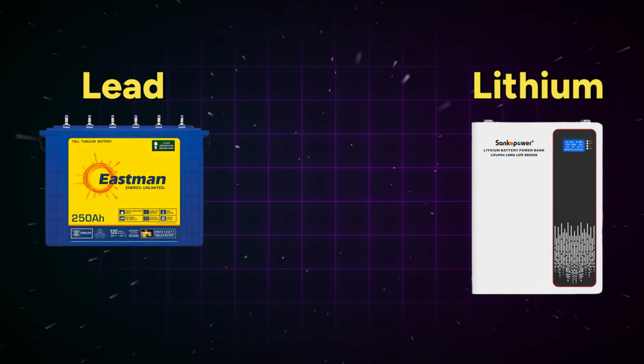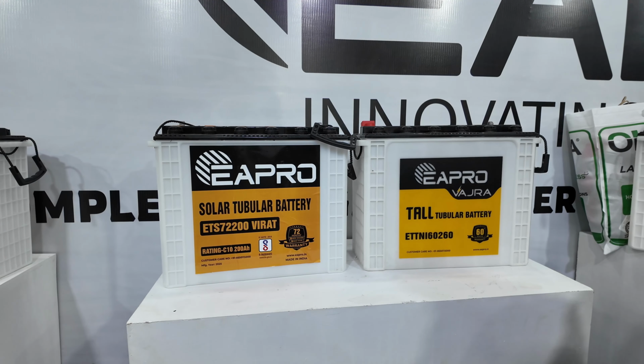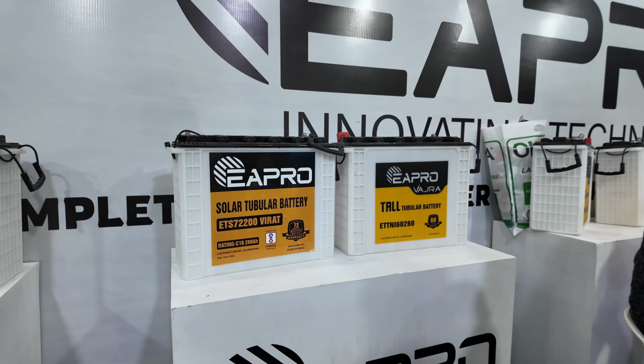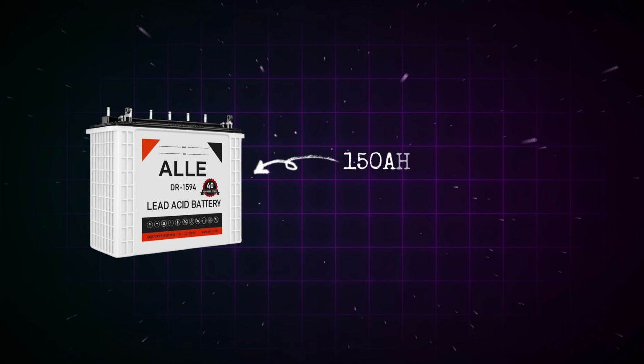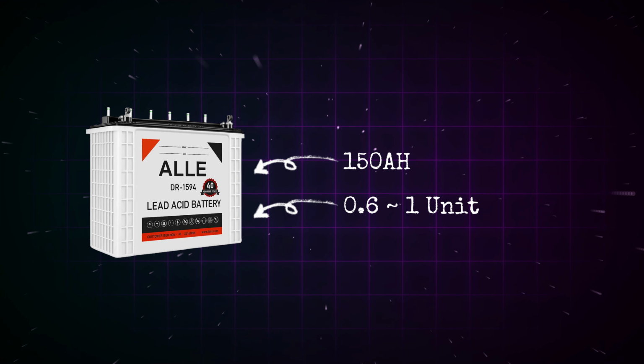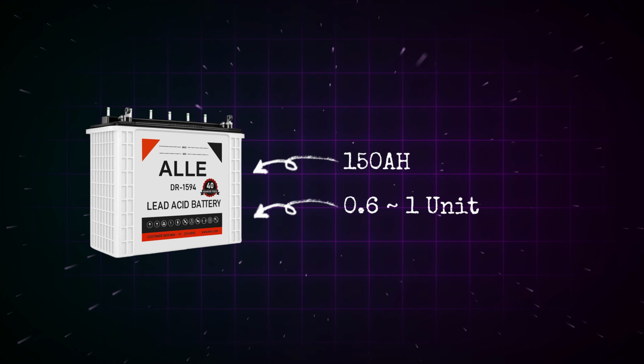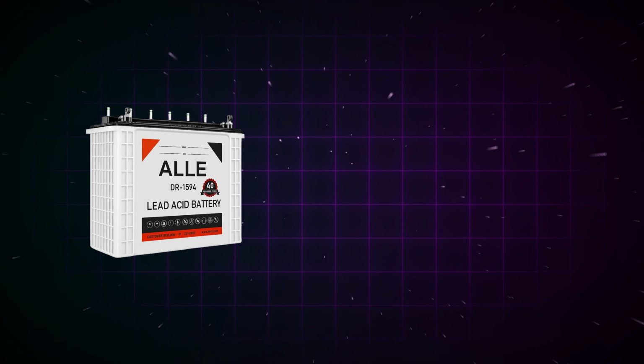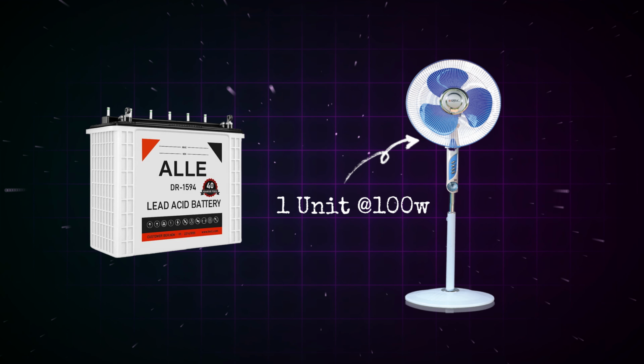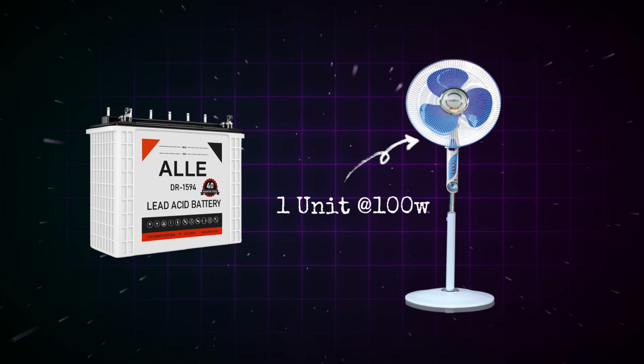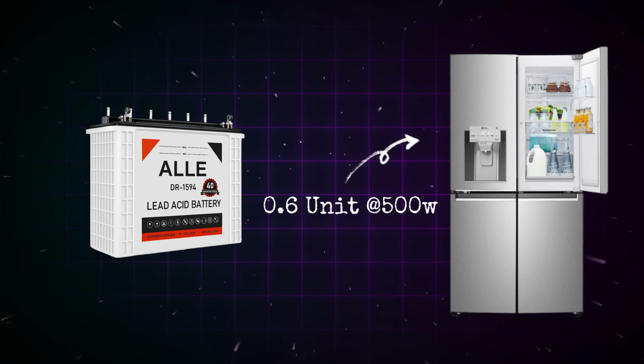Here on YouTube you will see many videos where you are shown a calculation that for so many hours of load you should take so many ampere hour batteries. That calculation does not work everywhere. That calculation works only when you run load according to the battery rating. Here let us talk about an example. From a 150 ampere hour battery, you can get from 0.6 unit to 1 unit of electricity. It depends on how much load you are running. If you reduce the load, that is, if your load is running around 100 watts, then maybe you will get 1 unit. If your load is running 500 watts, then you may get only 0.6 unit.